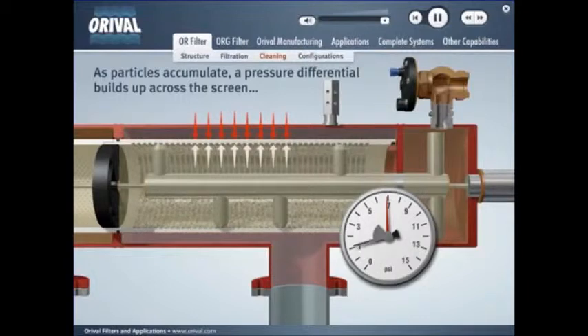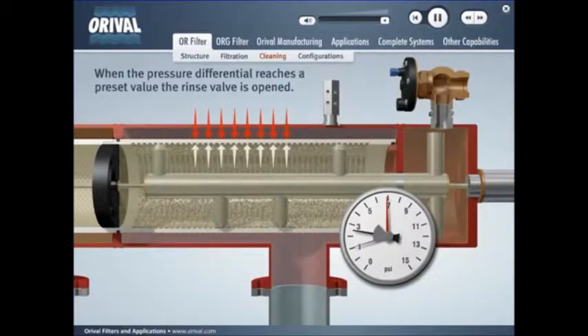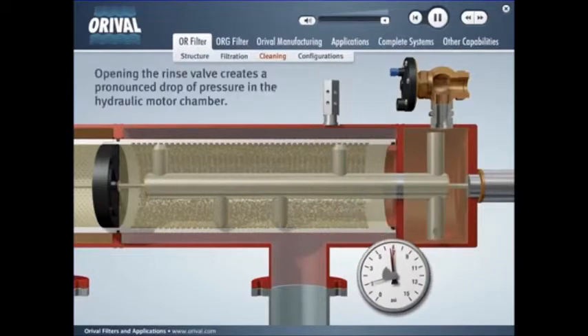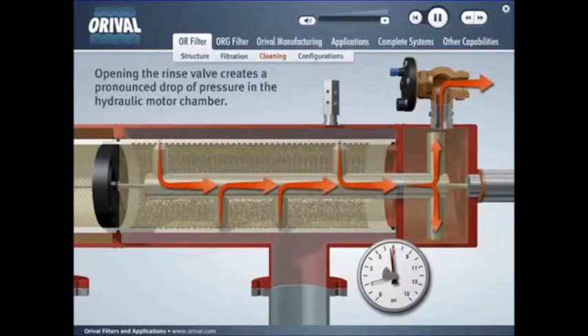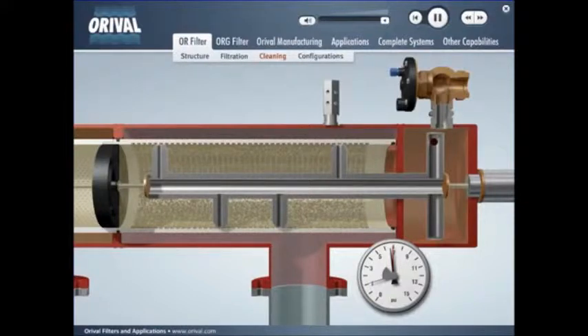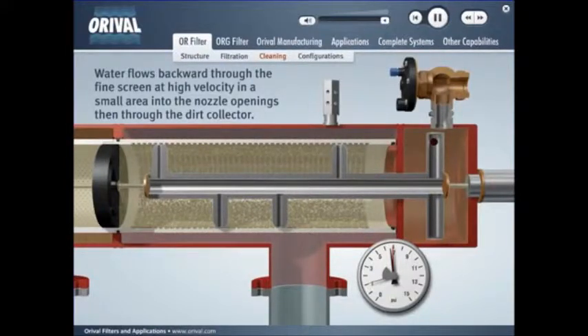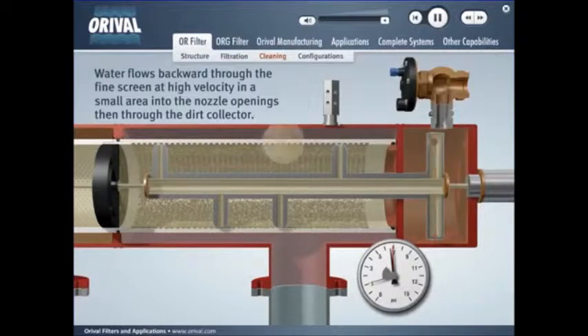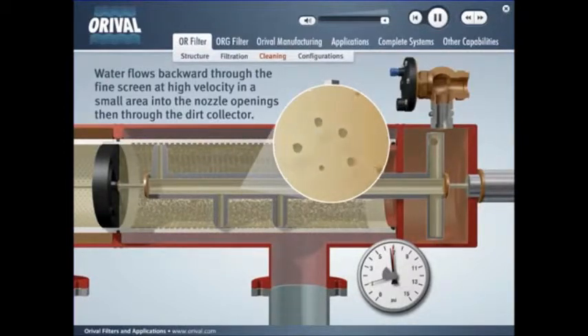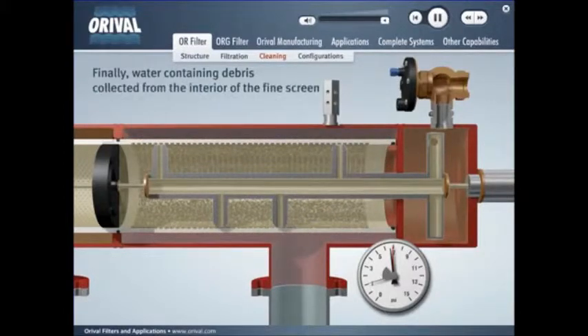As particles accumulate, a pressure differential builds up across the screen. When the pressure differential reaches a preset value, the rinse valve is opened. Opening the rinse valve creates a pronounced drop of pressure in the hydraulic motor chamber. Water flows backward through the screen in a very small area at high velocity and into the nozzle openings, then through the dirt collector and into the hydraulic motor chamber. Finally, water containing debris collected from the interior of the fine screen is evacuated through the rinse valve.